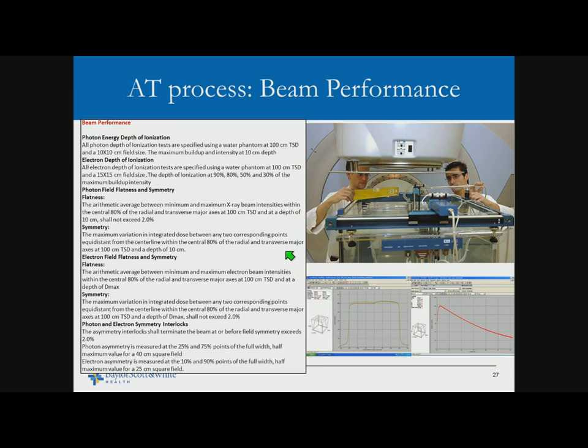Electron PDDs, flatness, and symmetry all need to be established. Varian tolerances differ from what TG 142 or TG 40 recommends — TG 142 moved to a performance-based approach for reasons like this. When performing measurements, you need a reference chamber and field chamber. The reference chamber accounts for fluctuations in the pulsed beam output — unlike cobalt, the LINAC is not a reliable radiation source — so dose falloff in the profile reflects only attenuation, not dose fluctuation.